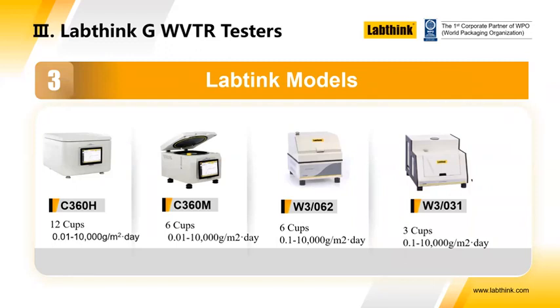And then there are different models for different applications. The C360 series can take 6 cups or 12 cups, has an accuracy of 0.01 for 10,000 grams per meter squared per day per atmosphere. W3062 has a capacity of 6 cups, slightly less sensitive than 360. And W3031 is a very basic instrument with 3 cups, which can only perform the wet method. The other 3 instruments, the 360s and the W3062, can perform both wet and desiccant methods. W3031 only performs the wet method or water method.